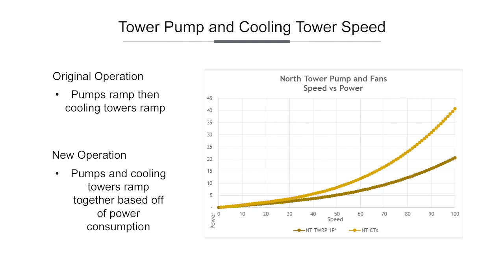Jason and team put tracking Fluke meters on the pumps and on the tower, watched the behavior, plotted it out, saw their behaviors over time, came up with performance curves, looked at it and said, well, wait a minute. Interestingly enough, in terms of the effective cooling that could be achieved, they found out that if they match the pump and the cooling tower and ramp them together, they got the same effective cooling as opposed to running the pump up to, say, its full 20 kW, and then starting to ramp up the tower. If tower and pump were both at, say, 5 kW each, they were getting the same effective cooling effect on the system. That was purely a watch the behavior of the system, plot it, track it, and then Jason putting his engineer mind to the problem, saying, hey, wait a minute, we think there is another way we can sequence these to trim the load.